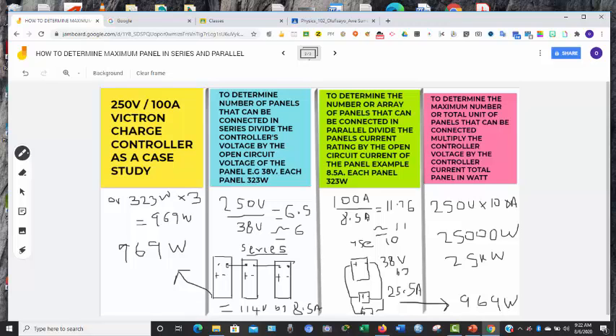How do I know the maximum panels to connect to a charge controller? Simply multiply the voltage of the charge controller with the current of the charge controller. So I have 25,000 watts, which is 25 kilowatts. So it means if I want to know the number of panels I can connect, like in this scenario now...